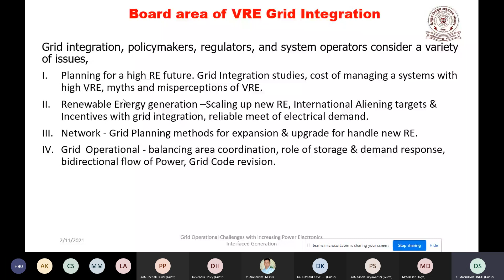These are a few things where this research is moving on, and moreover they are in the implementation stage also. And then wherever the grid code revision is required, or there may be the bidirectional flow of power once you install these resources on the distribution side. Otherwise you have the unidirectional flow of power typically, because your distribution system is radial. Your power comes only from the transmission to the distribution. But if you're planning some of this generation on the distribution side, then definitely there's a bidirectional flow of power. So these are the operational issues. So these are the broad areas I told about. When you integrate the renewables in the system, you have to take these carefully.